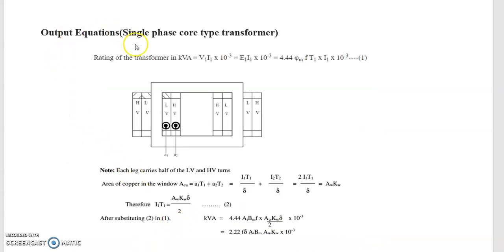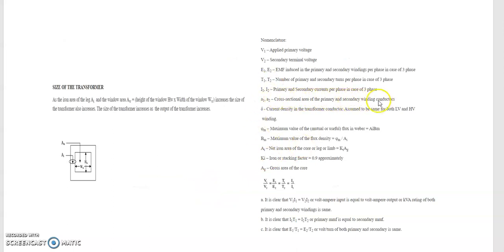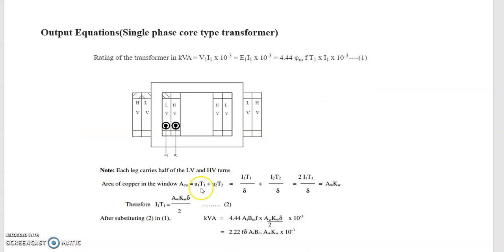We need to calculate the output equations for both single phase first and then three phase transformer. For the core type single phase, the KVA rating of the transformer is given as E1·I1 × 10⁻³. We have already derived the EMF equation. The area of copper A1 is the cross-sectional area of the primary conductor, so A1·T1 gives the copper area for primary turns. A2 is the cross-sectional area of the secondary and T2 is the number of turns of the secondary.